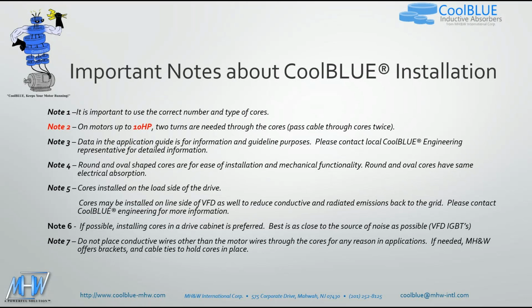The cores are installed on the load side of the drives. They can be installed on the line side of the VFD as well to reduce conductive and radiated emissions back to the grid. Again, if you're looking to do that, you definitely want to contact us. And generally, it's basically the same cores that you use on the output of your VFD. You can also use those on the input. But it's best that you would go ahead and contact us.